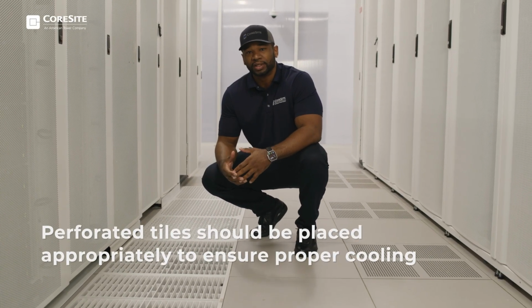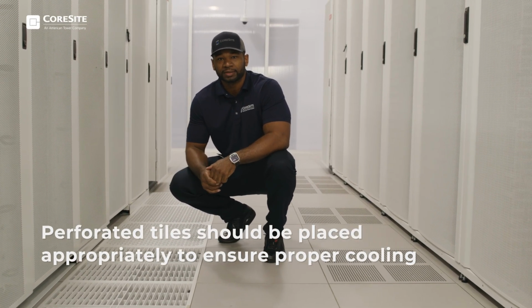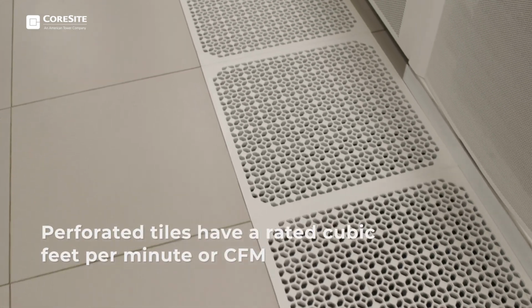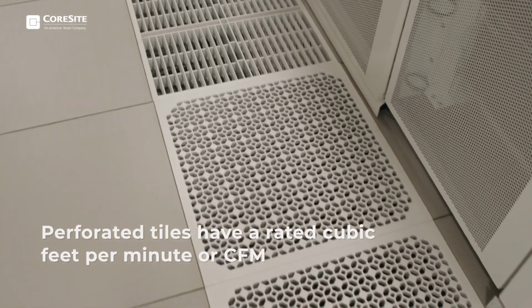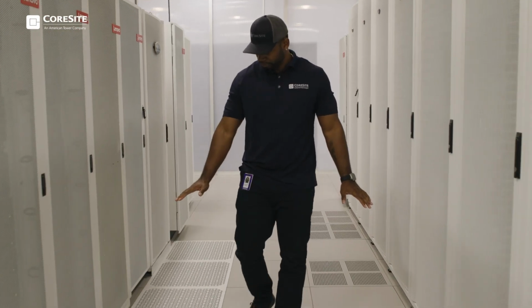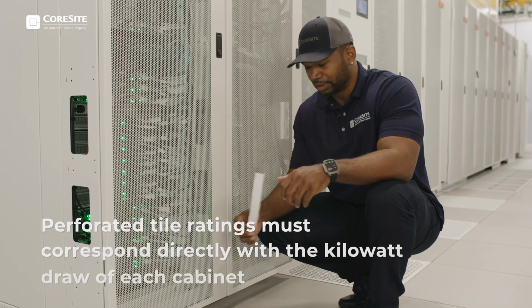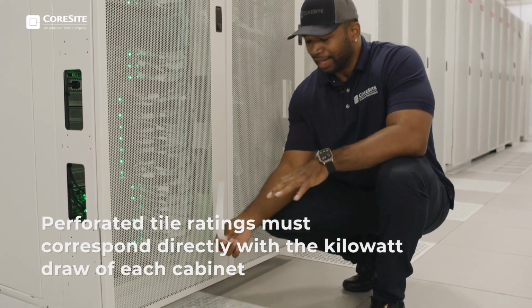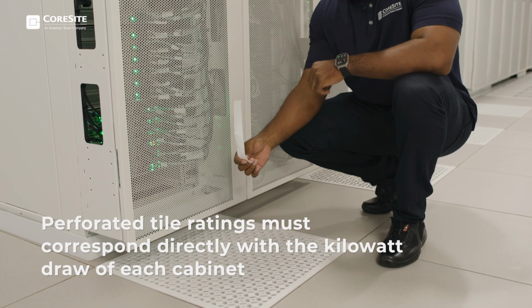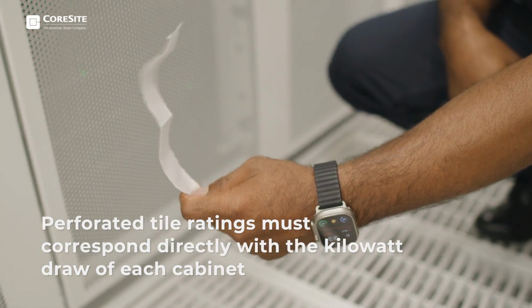It's extremely important that you place these tiles appropriately. Each perforated tile has a rated CFM, or cubic feet per minute, which is a measurement of the volume of air that passes through the tile. That tile has to correspond directly with the amount of KW that each rack is drawing.